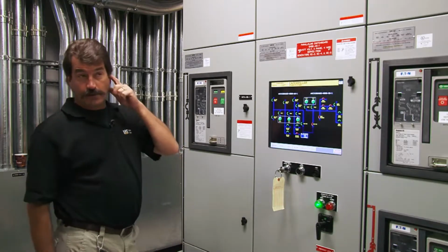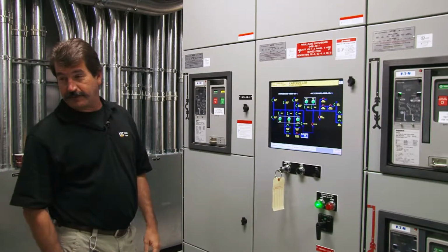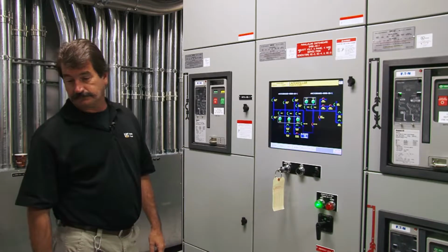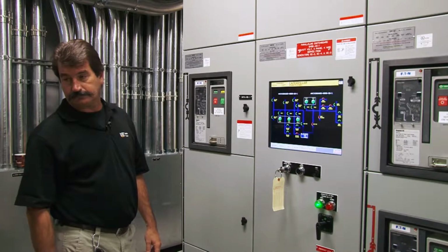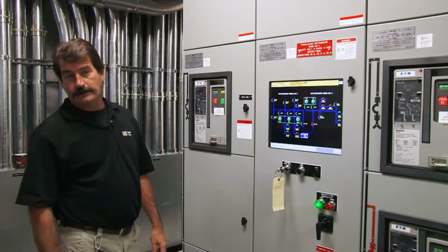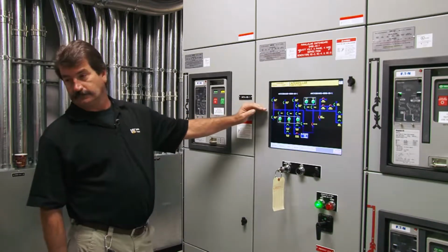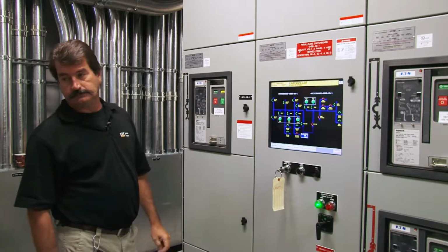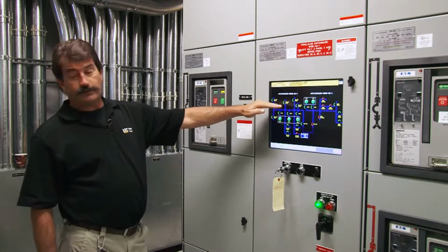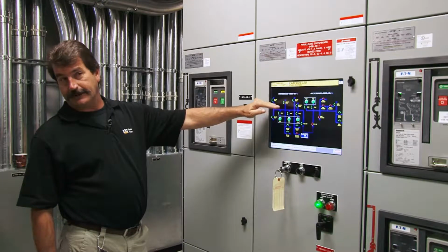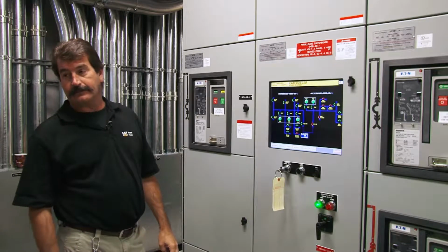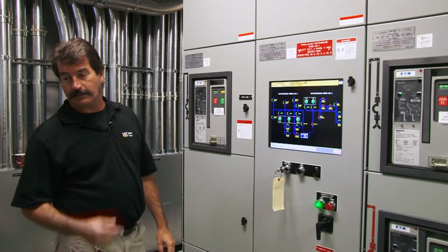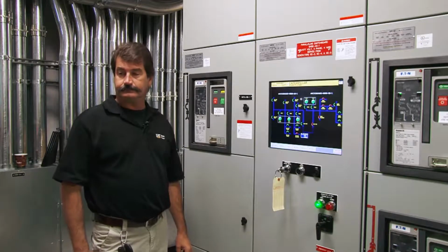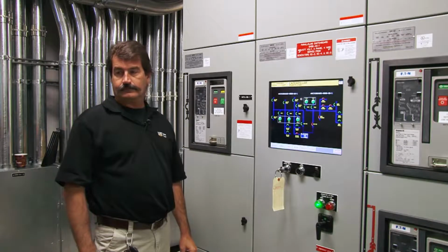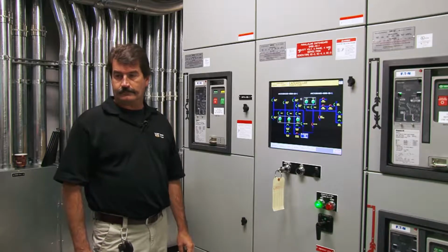Okay, and those are going to like chiller pumps and stuff like that? The chiller is going to all the circuits that were previously deemed normal circuits come in after. Critical circuits come up straight away without fail. The others come in sequentially. Now, are these going to ATSs also? No, those are going to switchboards. Okay. The normal switchboard out here. Switchboards up on the 3rd floor, picking up everything that wasn't previously picked up on the ATS.